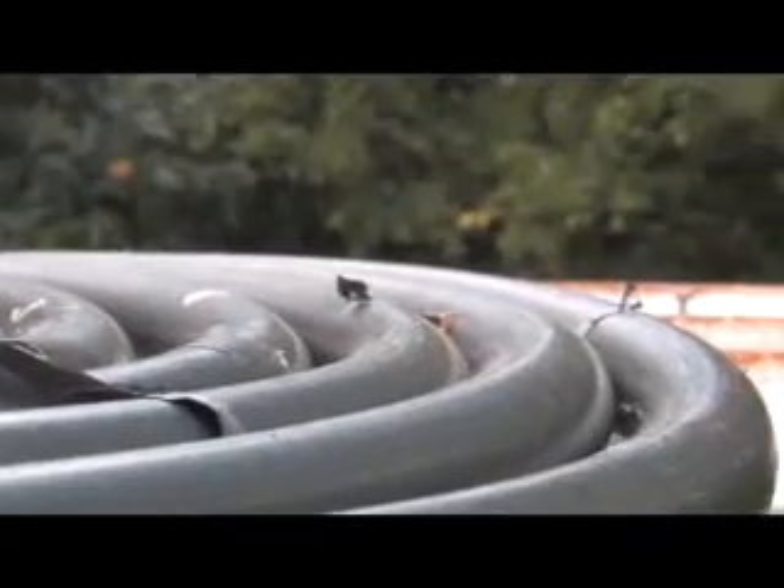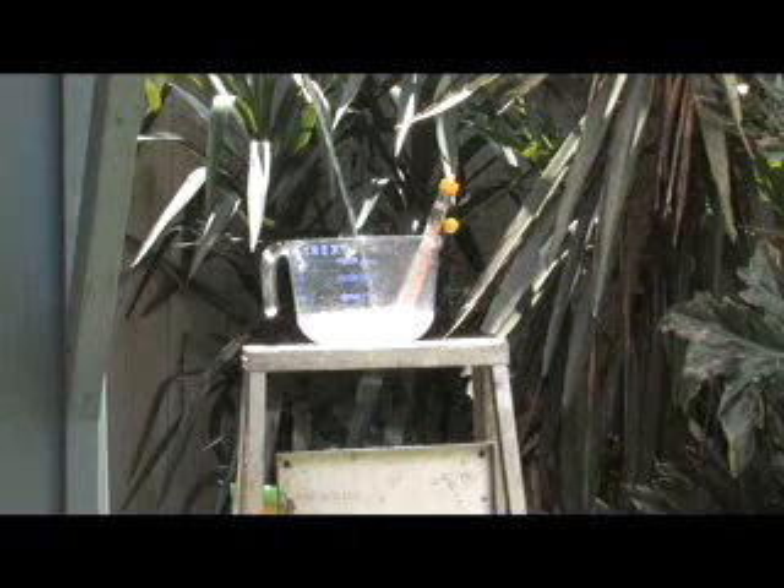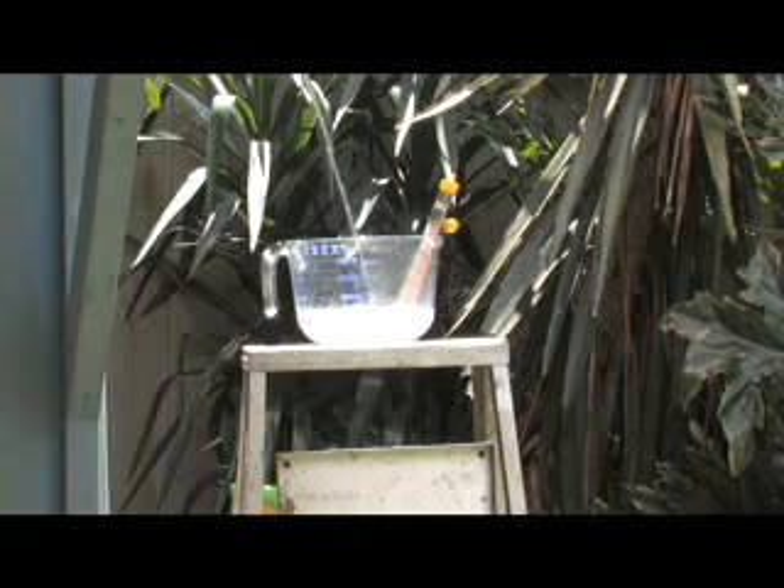Spiraled neatly, the black tape will be removed once water is added to weigh down the tubing. The heated water exits out the side of the carport closest to our house, where hot water is channeled through CPVC underground and into the cold inlet of our electric hot water heater. The extra spigot provides an outlet to drain the system for easy maintenance and also provides instant access to solar-only hot water.